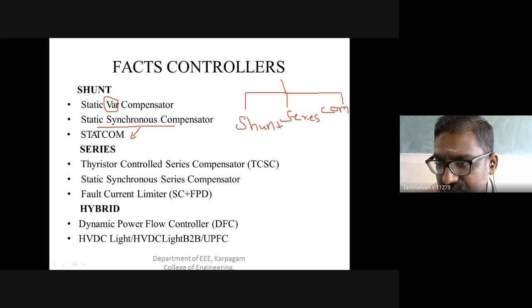TCSC stands for Thyristor Controlled Series Capacitor, sometimes also referred to as a thyristor switched capacitor. It consists of series capacitor banks shunted with a thyristor controlled reactor, which together provide smooth variable series capacitance.